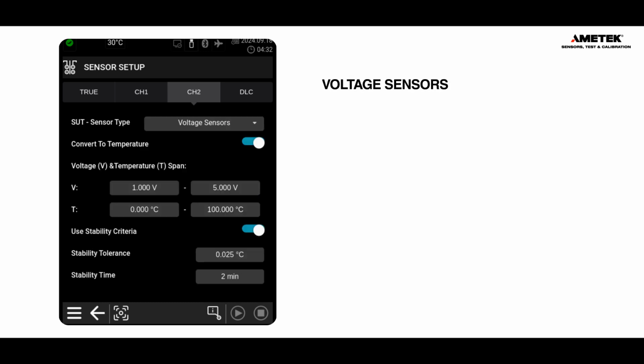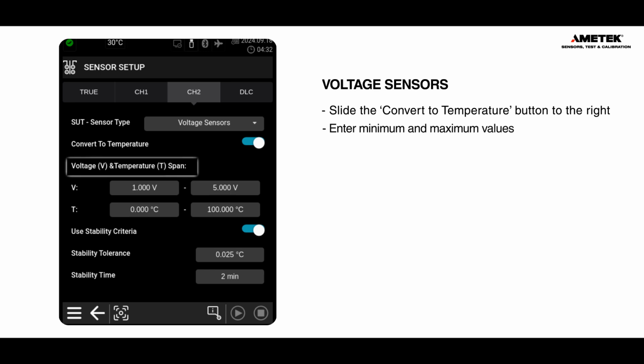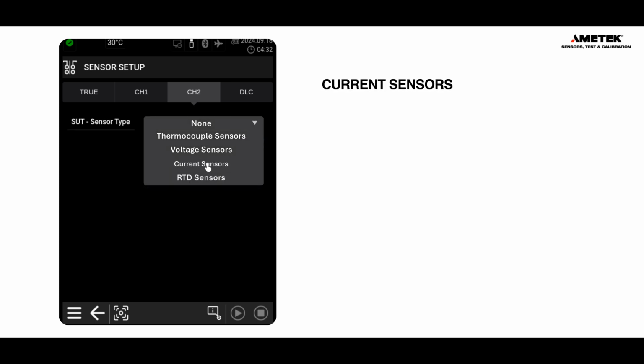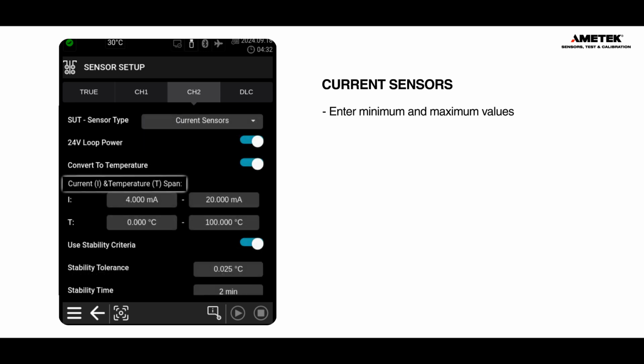Voltage sensors. Convert to temperature. When this function is activated, inputs are converted into temperature. If it's not activated, no conversion takes place. Voltage and temperature span. Set the minimum and maximum values for voltage and the corresponding temperature using the numeric keys. Current sensors. Current and temperature span. Set the minimum and maximum values for current and temperature using the numeric keys. These define the span for calibration or measurement.